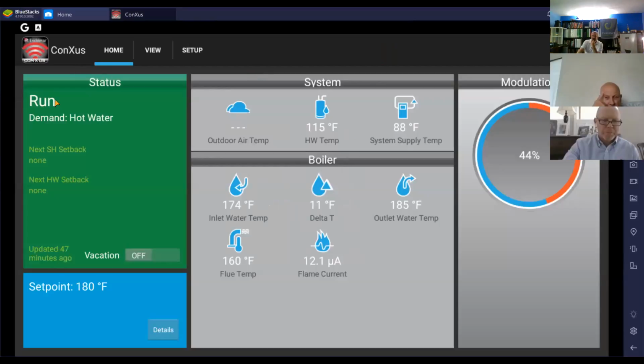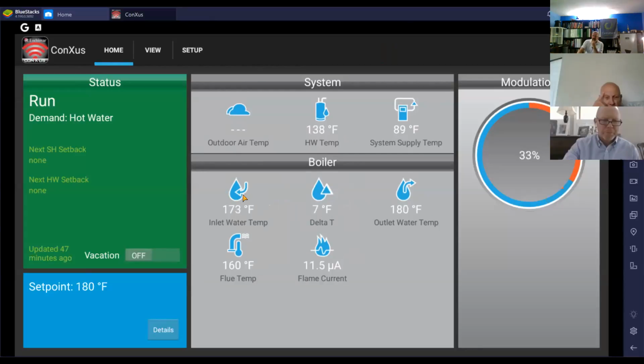So I'd select it. This boiler is actually running in domestic hot water mode as it is. So there we have run - we have a hot water demand, got a set point of 180, modulation rate of 44%, and it's now 33%. It's giving me all the temperatures of what's happening.